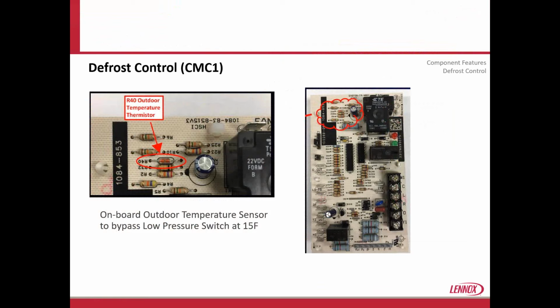And then the next thing that's changed as well is when we enter defrost mode, we no longer look at that sensor either. Okay, and for the first 10 minutes of run time after the defrost cycle is over, we're still bypassing that temperature, that low pressure sensor. So it's not going to have any nuisance trips due to defrost, and that's what we had on the heat pump control on the package unit.